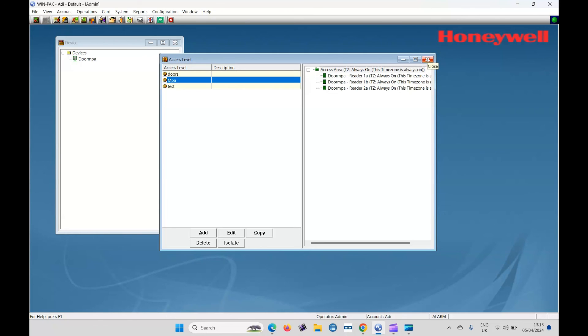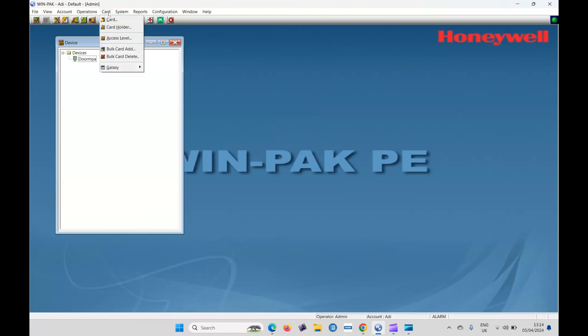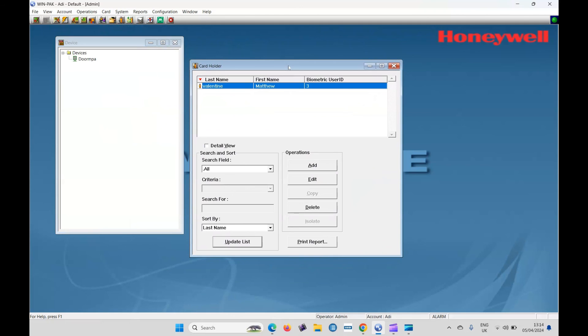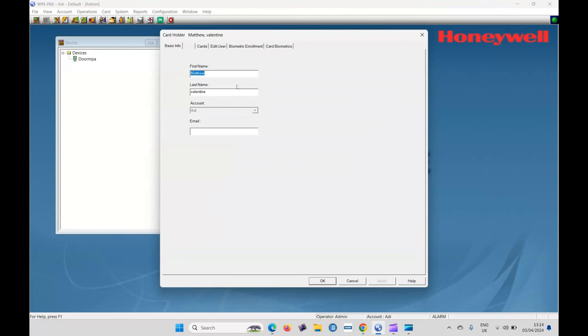That's the controller now configured and added to Winpak. And we can test its functionality by adding a card. Now I've got a card here. I know the site code. I actually know the card number as well. Let me double check. I got the right one. Six, five, five, zero. So now if I go to card holder. I'm already there. In fact, I bet this card's already on. So there's my name and details cards. That's a shame. It's good that it saves me typing it out again, but my card details were already there.